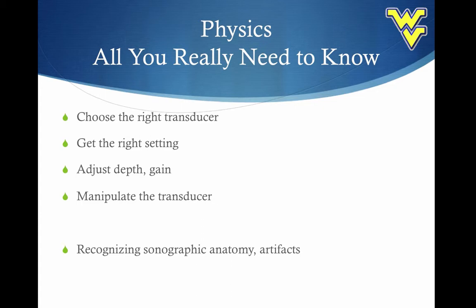So if I boil this down to one little slide of what you really need to know and what I want you to get out of this with physics and operating the machine, you need to be able to make sure you pick the right transducer for the job that you're trying to do. You need to get the machine on the right setting. So if you're looking at the abdomen, get the abdomen. If you're looking at the heart, choose cardiac or whatever. You need to adjust basically two buttons on the machine. There's a few other buttons I'll teach you about, but two things that you need to fairly regularly adjust, and that's your depth and your gain. Everything else is like an on button or an enter button, okay? So two buttons that you're going to adjust, depth and gain.